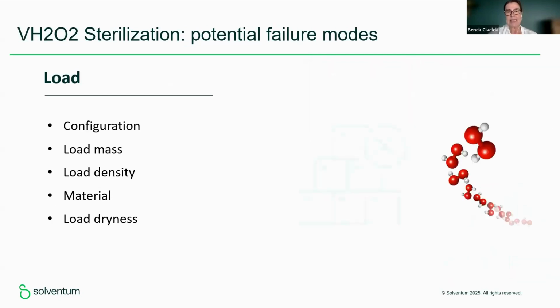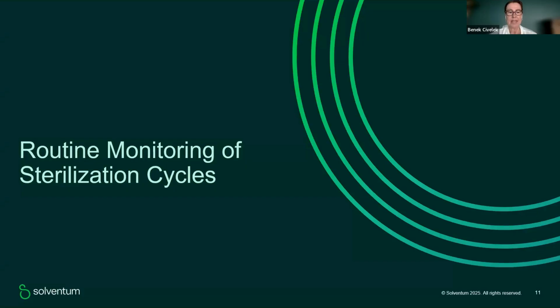Hydrogen peroxide is another technology. This is the low temperature technology we are using most these days. Hydrogen peroxide is not as robust as steam, because it does not have the real ability to reach narrow lumens and long lumens. Therefore, load configuration, the materials, and also the dryness, the density, and the weight are all important for hydrogen peroxide sterilization success. The routine monitoring of the cycles.